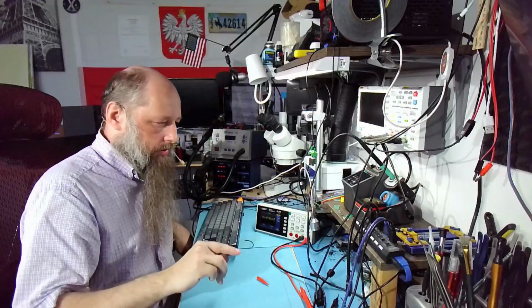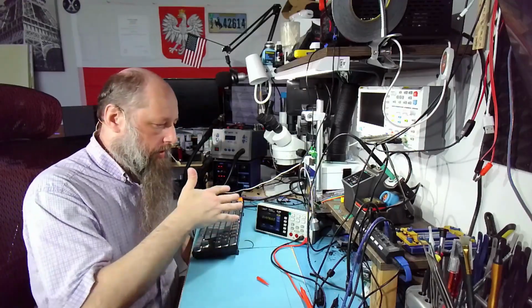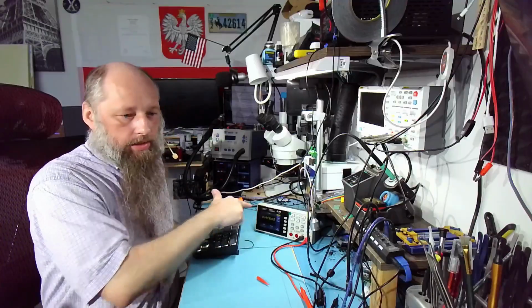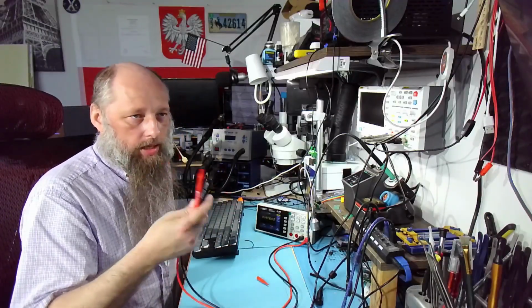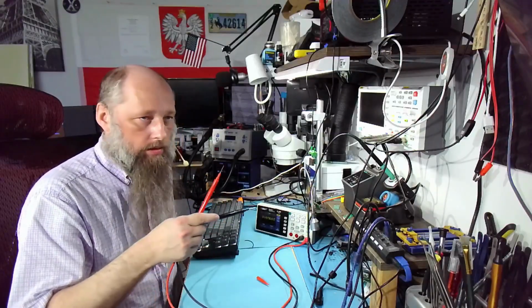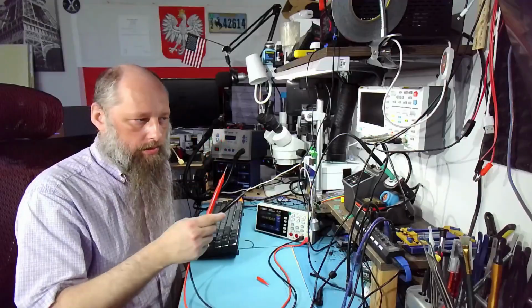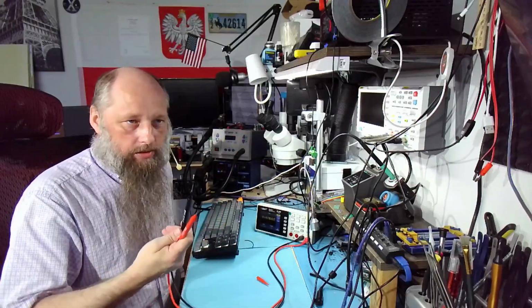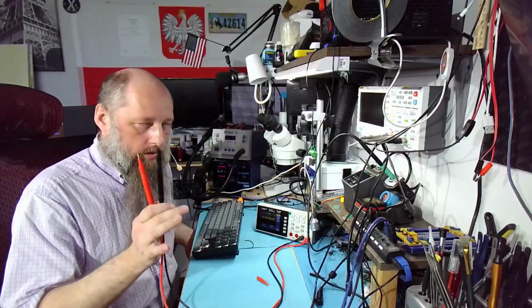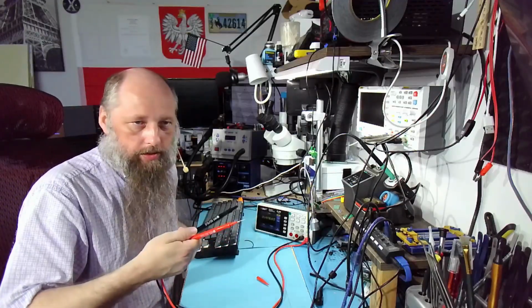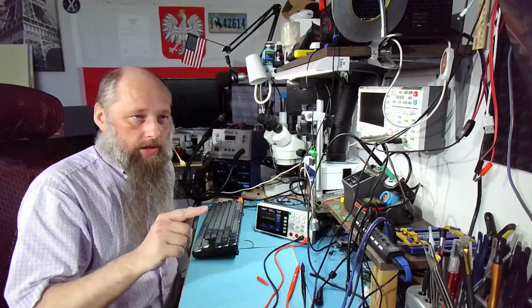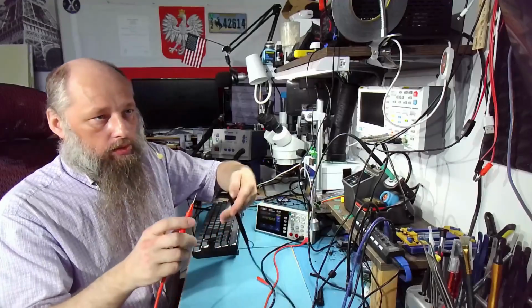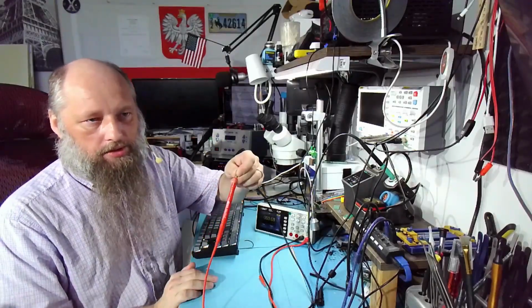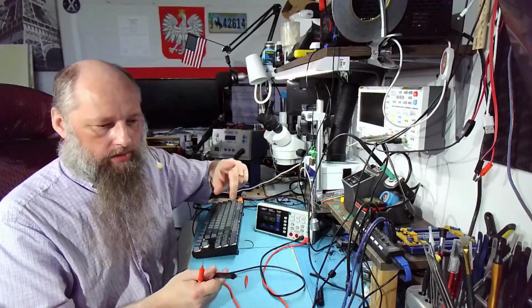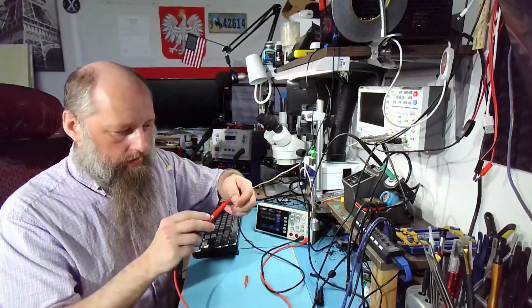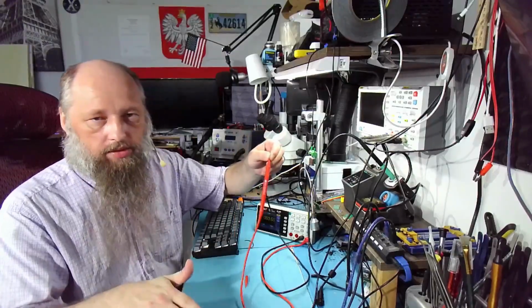Now, there's also going to be additional functionality regarding calibration. As you can see now, my probes call it 60, 70, maybe 80 milliohms. You'll be able to adjust the software so it just reduces that resistance or changes the voltage based on your probes. Obviously, you put it in manually. Or I'll just have a button. You press the button, you short the probes, and that's going to be our 0, right? So just like we calibrate the ESR meter, the same with this one. We're going to short the probes, click the button, and that's our 0, right?